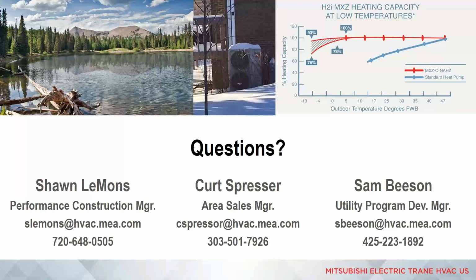And one of the big studies indicates that by moving to heat pumps and even using what is most common out there today, 410A, which has a really high global warming potential, we still overall lower the greenhouse gas emissions pretty significantly. I don't have the numbers, but in harmony with that, we're going to be moving away from 410A pretty rapidly over the next few years. There are refrigerants out now like R32 that have a GWP, I think around 650 or something like that. They're pretty low compared to 410A, which is over 2,000.